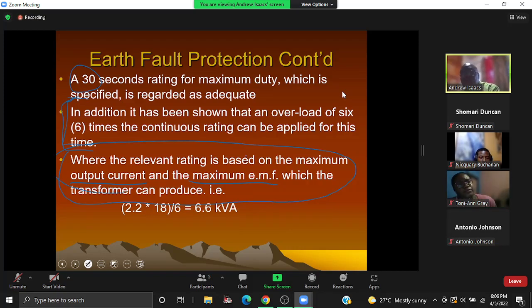in terms of the maximum voltage, because we calculated the maximum current. But as I said, when we looked at the voltage, that voltage collapse, we looked at the normal terminal voltage, which was the 13.8. But we know that it can go up to 18. So we are using that maximum. So it's not the 22 that we are rating it on. All right? So it would be 2.2 times 18 over 6. So that would be 39 point something. All right, 36, so it would be 39.6. We divide that by 6, we get 6.6.